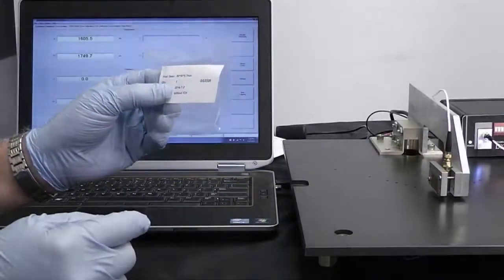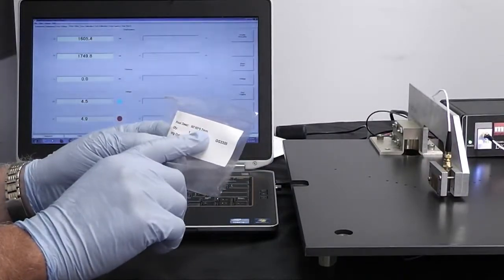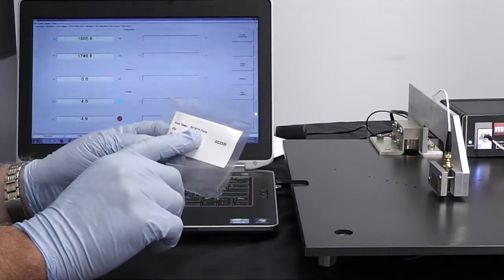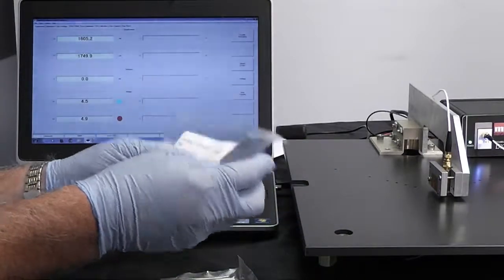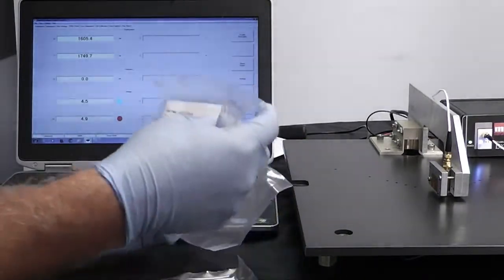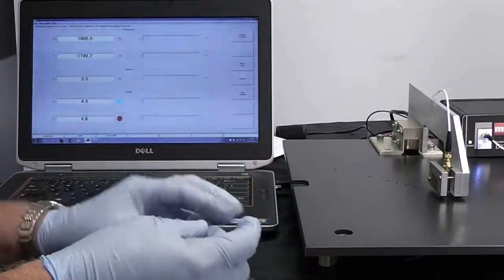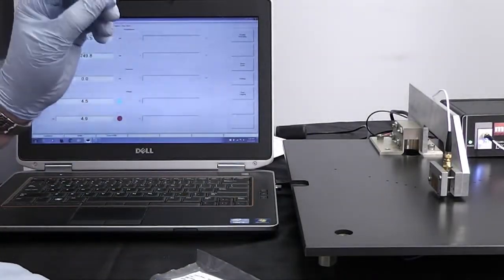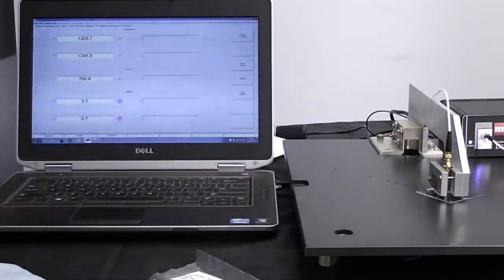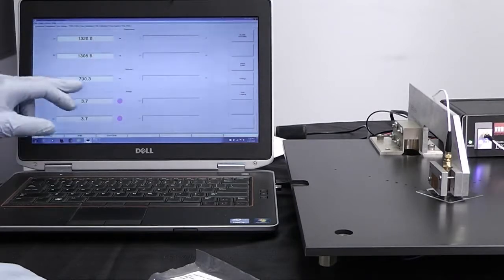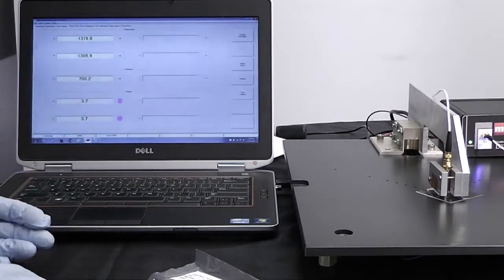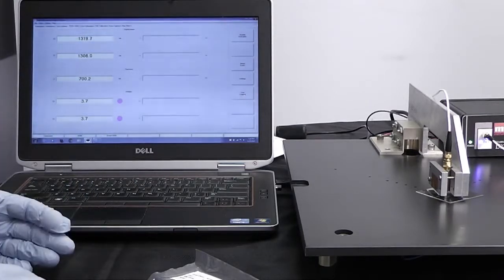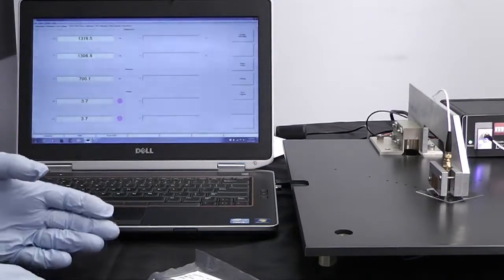Next we're going to measure Gorilla Glass. The manufacturer of the glass was kind enough to give us the thickness. But the accuracy is only to, in this case, probably about 10 microns because they don't go past the second digit on these. So, I've already set up the slope factor. I've checked it before. What we do is we put the first sample under here. And we've entered that sample thickness in here and then calibrated on that. So every time you start with a known slope factor and a sample, you have to calibrate the sample to the system. And that's fairly easy to do. You just take one known thickness and you go in and you go to the thickness calibration tab as we've seen before.